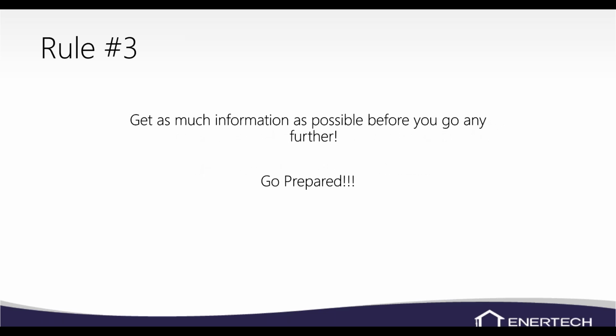Make sure you get as much information. If you've got some startup sheets, you may want to take a look at those. You can give us a call in tech support with the serial number, and we can look and see if there's been any what we call incidents or calls to tech support on that unit. We can also look up any kind of warranty claims that have been made on the unit or anything that's really happened to the unit. We have basically a unit snapshot we can pull up with the serial number. So we can see if, you know, a TXV has been replaced a couple days ago, or they had a compressor replaced 5 years ago, or anything like that we can see on that unit. So just give us a call and we'll pull that up with the serial number. We don't necessarily have to have the model number. We can get the model number if we have the serial number.